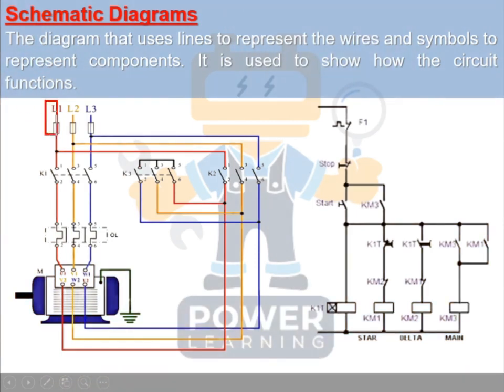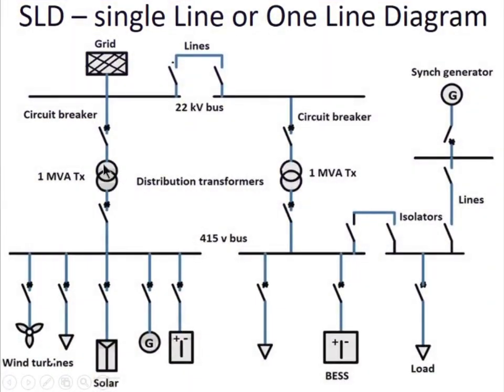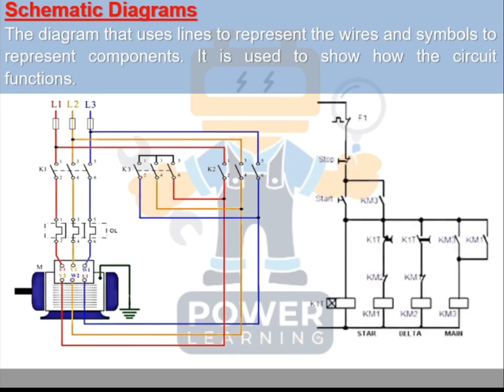In a schematic, each component is shown separately — for example, three fuses and three lines are each shown individually. Comparing this to a single line diagram, an SLD shows only a single line for a multi-core cable without detailing each conductor. In a schematic, every component with its symbol and connections in the circuit is shown in full detail, giving a complete picture of the panel or device.